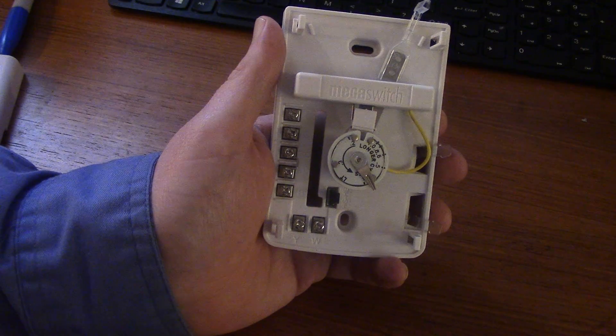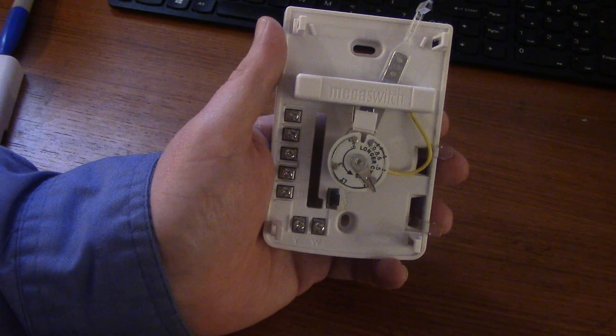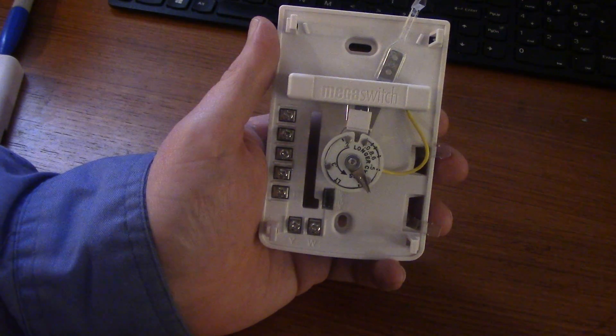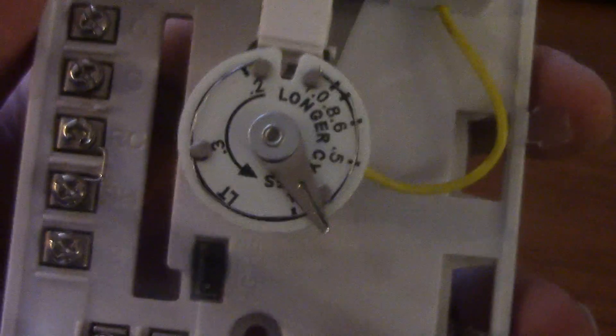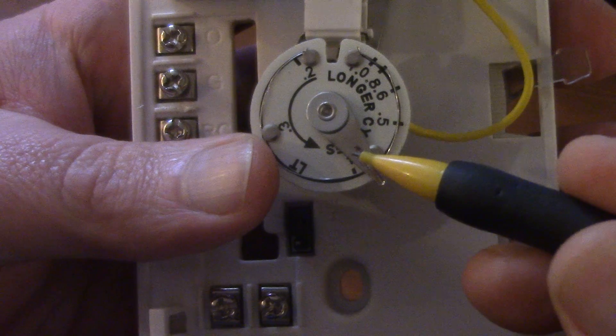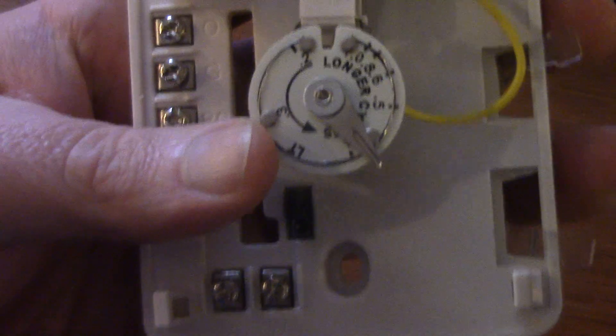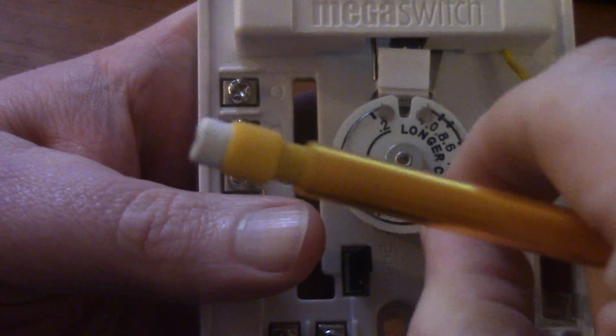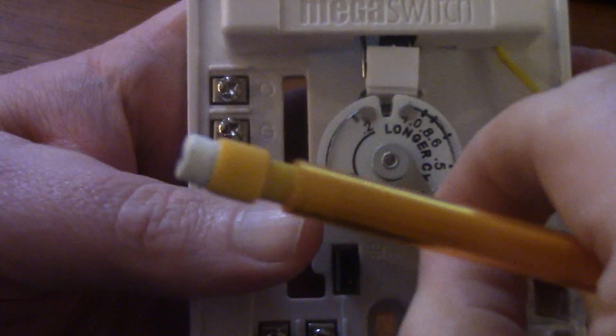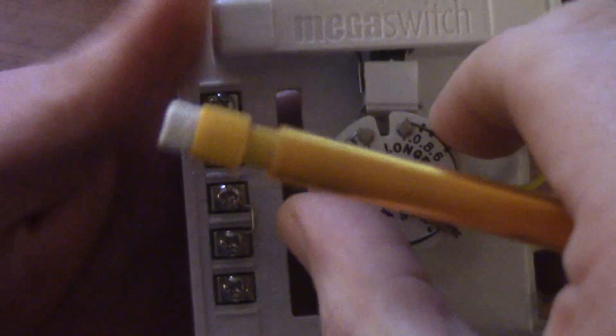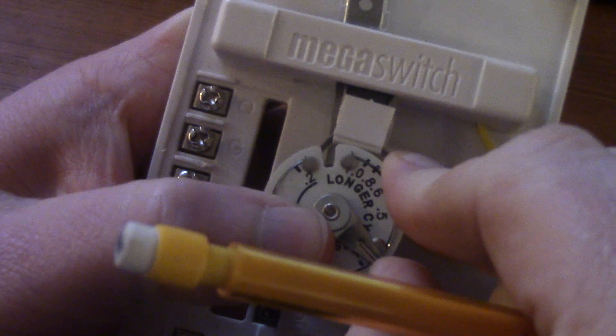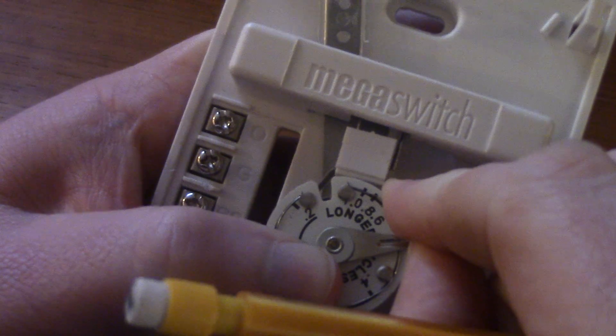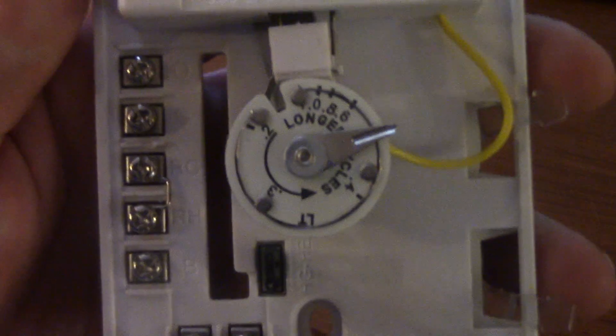If you get let's say 5 amps, you take that 5 divided by 10 to get 0.5. Now if I can get it here adjusted - you see where it says 0.5? That's where this little indicator must go for it to operate without overheating the house. You can't just take that and turn it because see what happens when I do that - you turn the whole thing or this whole center dial will turn. You hold it in place and just like that we have set the heat anticipator correctly.